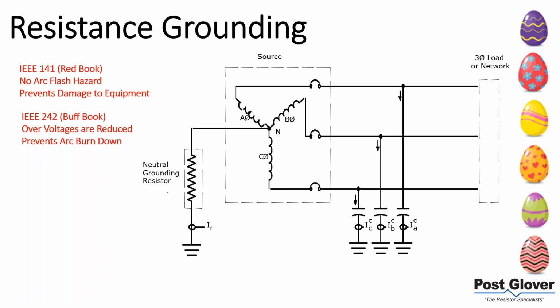So if you want it to be 10 amps, for example, with high resistance grounding, you could use a 10 amp resistor there. There are a couple of caveats in resistance grounding, but the one we'll talk about right now, in terms of design considerations, is that you need to make sure the current associated with your resistance value is higher than the capacitive charging current. Remember, I said that ungrounded systems have an overvoltage condition, but you also have the current associated with that leaking to ground. It's very small, but you need to make sure this resistor has a higher current, basically the path of least resistance. You have more flow through here. Therefore, you don't have the overvoltage situation that you would with an ungrounded system. So that's the main issue you need to solve when designing something like this.